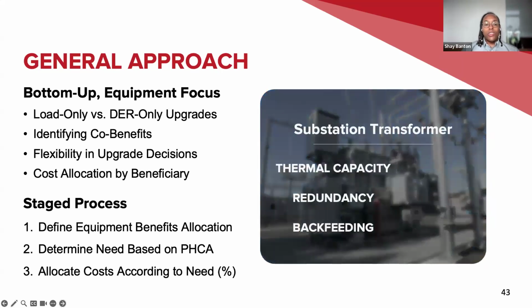Real quick, next slide, you'll see a little example of benefit distribution for a typical substation transformer. To define these co-benefits: a transformer itself has thermal capacity benefits, which benefit both DER and load, since they both have current, either injecting or absorbing it, and you need something large enough to accommodate that current.